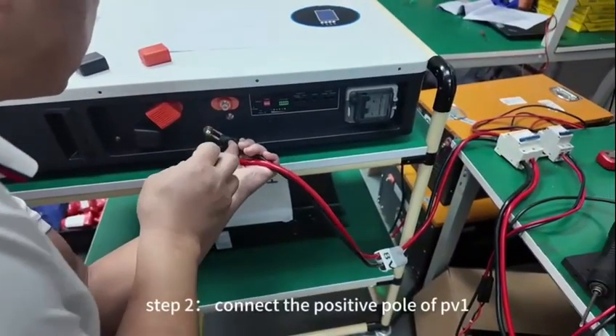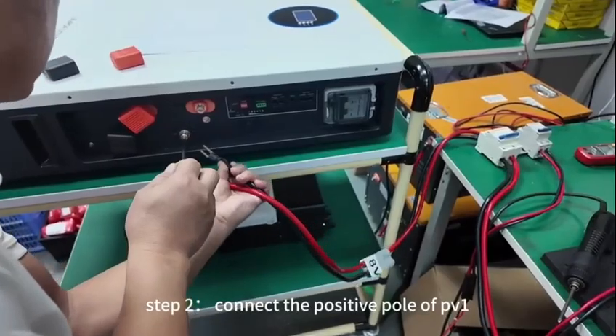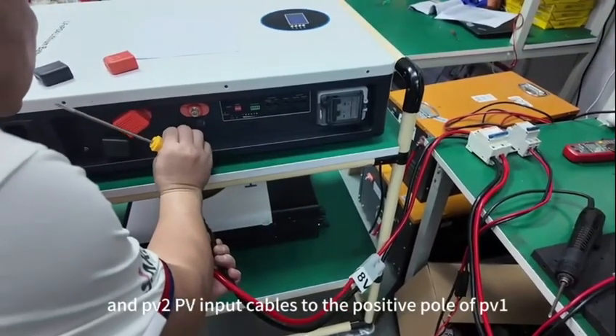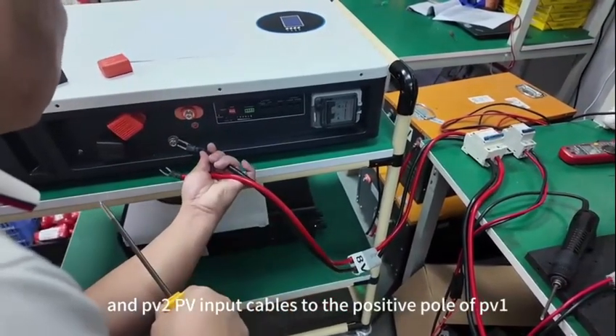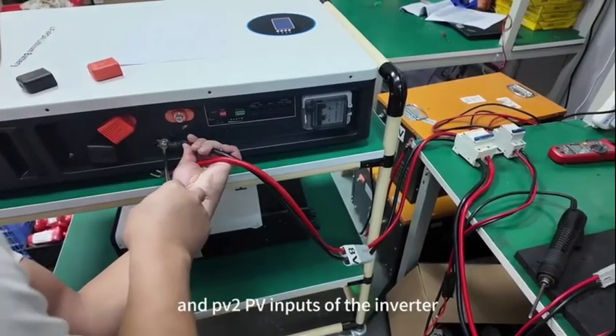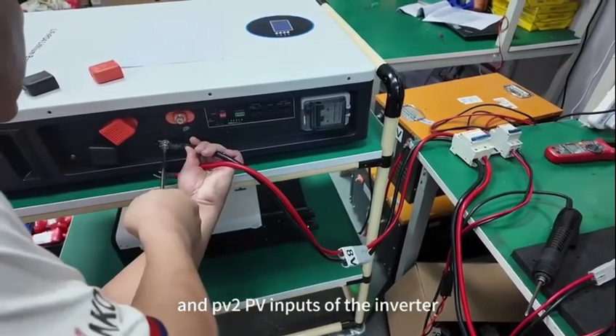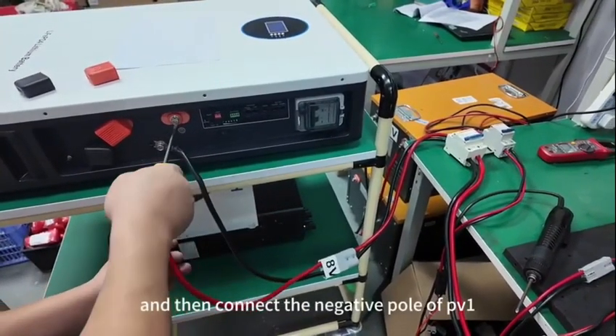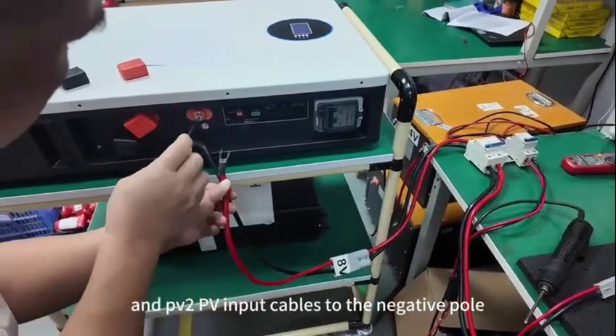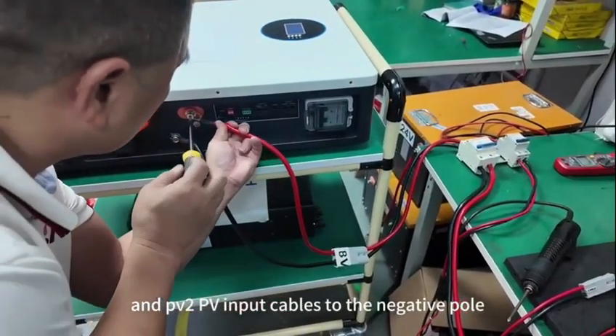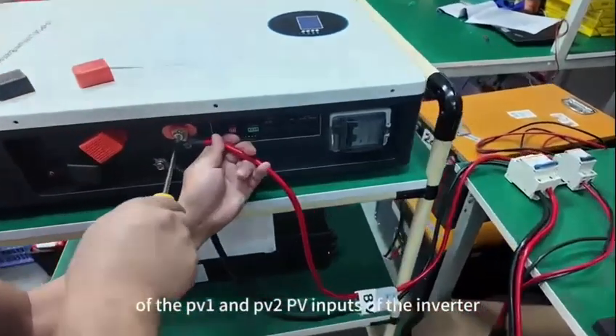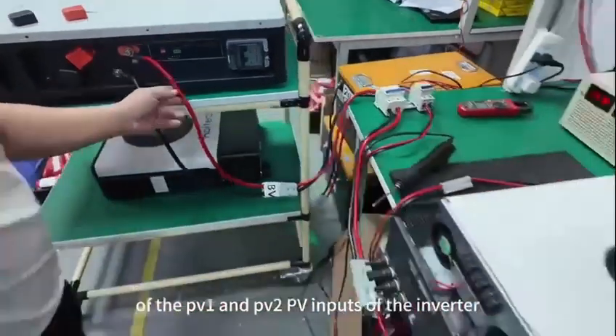Step 2. Connect the positive pole of PV1 and PV2 PV input cables to the positive pole of PV1 and PV2 PV inputs of the inverter, and then connect the negative pole of PV1 and PV2 PV input cables to the negative pole of the PV1 and PV2 PV inputs of the inverter.